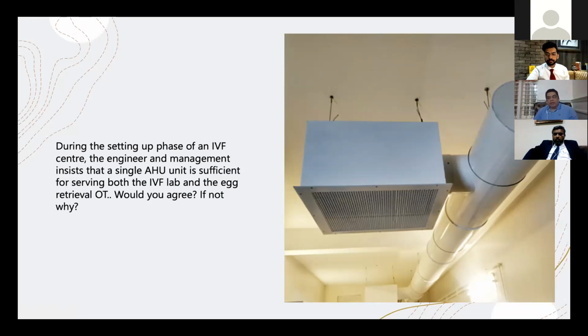So that's a very important point, that the anesthetic gases are a big source of VOCs, which we tend to overlook and forget about. Because you could argue that no disinfectants are used, or that all disinfectants used in the OT are also embryo safe. But what to do about the anesthetic gases? And the second important thing is that 95% of the clinics in India still use the box incubator with 5% or 6% CO2. And the rest, 95% of the air inside that box incubator, is derived from the room air. So whatever is in there finally dissolves into your oil and into your culture system. And if it is a micro-drop culture system, the concentration will be higher in the micro droplet. So you are saying it is a very good idea to have a separate AHU for the culture room.